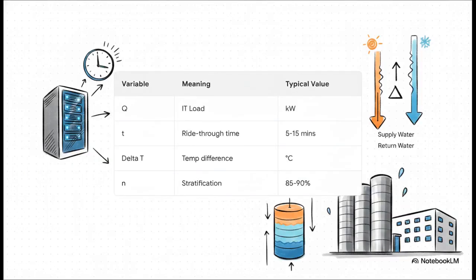So the crucial point really comes down to this. Just how big does this tank actually need to be? You definitely don't just guess. You have to calculate it precisely to save millions in hardware. Engineers take Q, which is the total IT load of the data center in kilowatts, and they multiply it by T, the target ride-through time, say 5 to 15 minutes. Then they factor in delta T, the temperature difference between the supply and return water, and finally divide it all by N, the tank's stratification efficiency, which is typically incredibly high, sitting at around 85 to 90%.